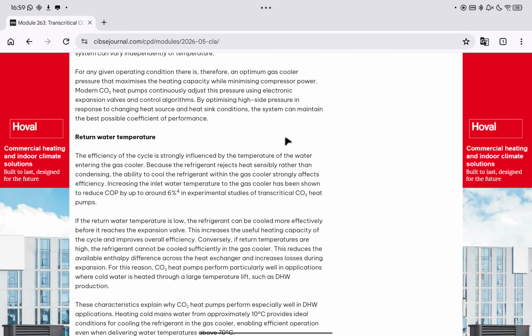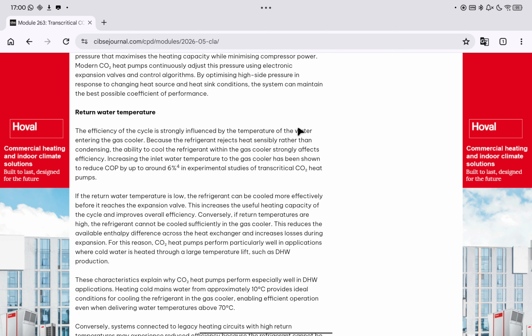Return water temperature. The efficiency of the cycle is strongly influenced by the temperature of the water entering the gas cooler. Because the refrigerant rejects heat sensibly rather than condensing, the ability to cool the refrigerant within the gas cooler strongly affects efficiency. Increasing the inlet water temperature to the gas cooler has been shown to reduce COP by up to around 6% in experimental studies of transcritical CO₂ heat pumps.